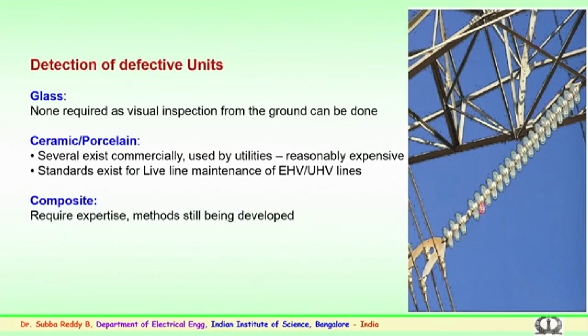So, what happens in the field? You can see here a string of glass insulators, where at a particular location an insulator has been shattered. This is the line end of the string, and this is the tower end, that is the ground end. This is the line end where 4 conductors are there. So, what happens when these insulators are shattered or damaged very near to the line end, how the potential changes or how the field gets modified, and whether this could lead to flashover. It is a very important phenomenon.